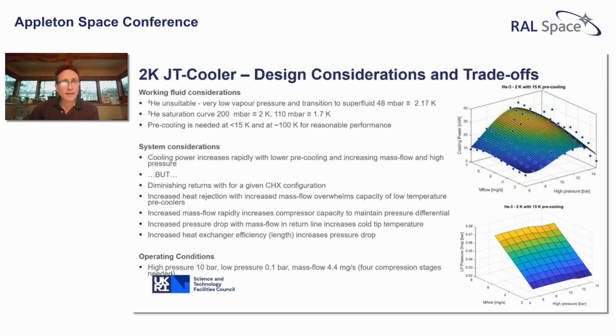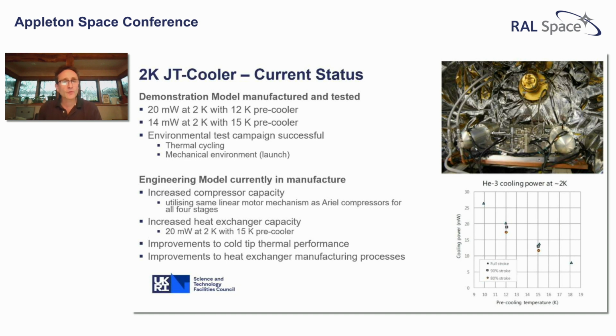Increasing the mass flow can completely overwhelm the capacity of the low temperature pre-coolers. You also need to increase the compressor capacity if you do that. And there's a consideration of the pressure drop down the line, which is extremely important. But nevertheless, we found an operating point, and we've been developing a cooler for that.